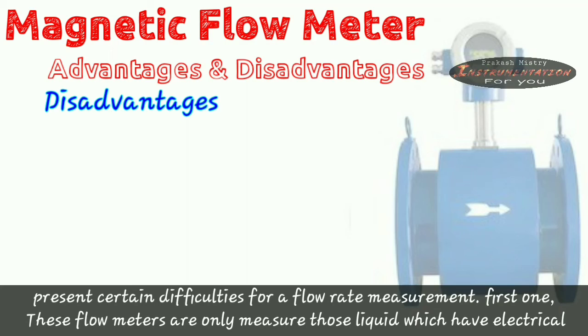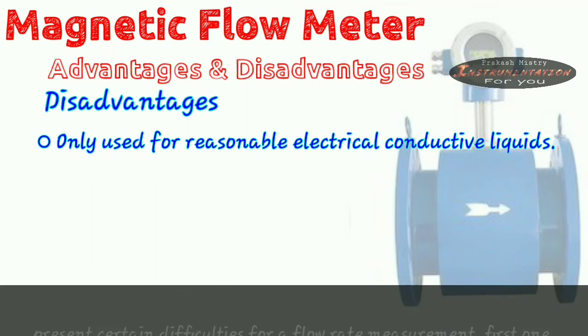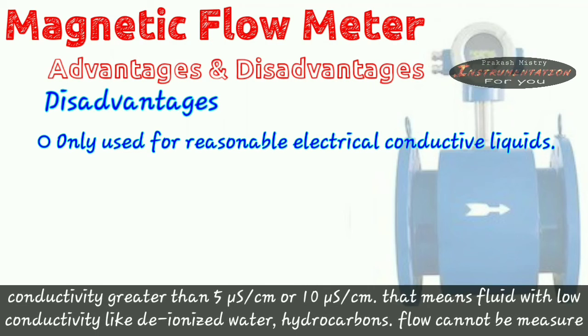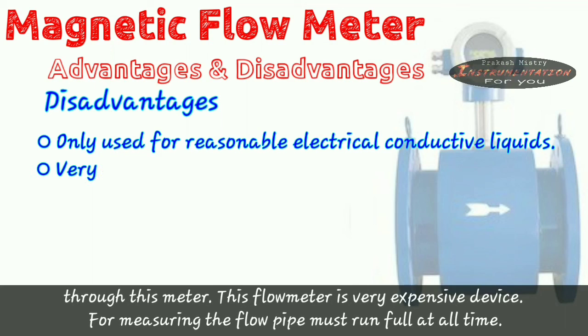First one, these flow meters only measure those liquids which have electrical conductivity greater than 5 microsiemens or 10 microsiemens. That means fluid with low conductivity like deionized water, hydrocarbons flow cannot be measured through this meter.